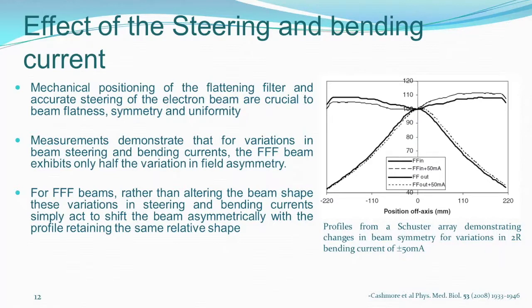Our flatness and symmetry will go off, and there will be non-uniformity, and you need to keep worrying, meddling with it, and keep changing it. So positioning should be very accurate. Now, if you don't have a flattening filter, you don't worry about the positioning of your flattening filter and the accuracy of it. But how does the steering affect your profile when you don't have a flattening filter?